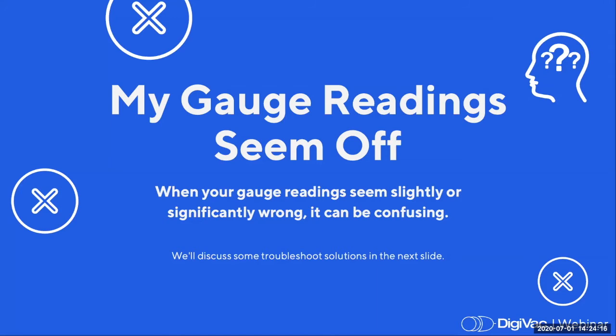So what if your gauge is powering up and reading vacuum, but you think that the readings are inaccurate? We'll troubleshoot these gauges in the next slide. Inaccurate readings can be caused by faulty equipment, leaks, contamination to the sensor, just to name a few. So here we'll discuss some troubleshooting solutions.